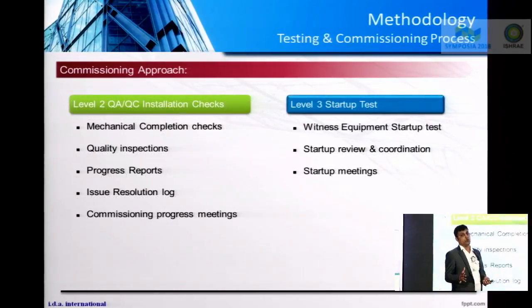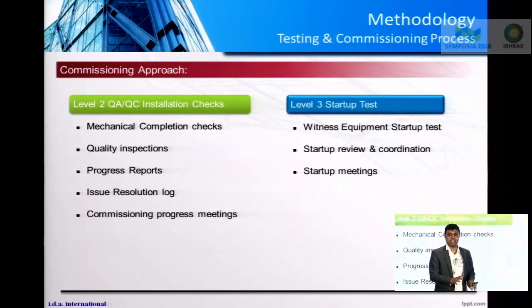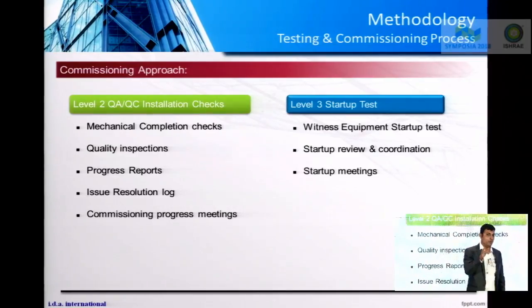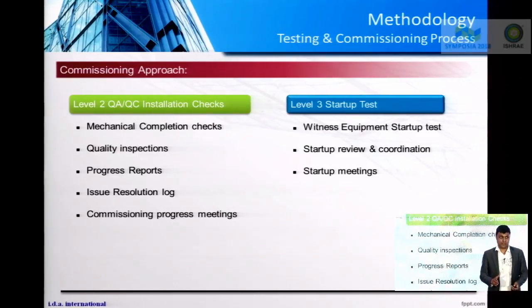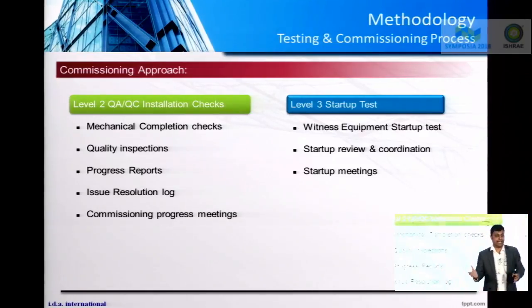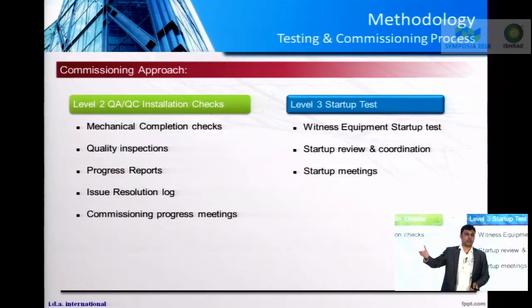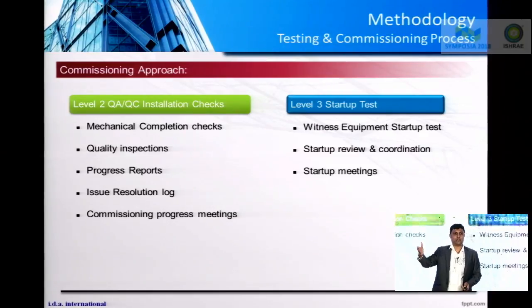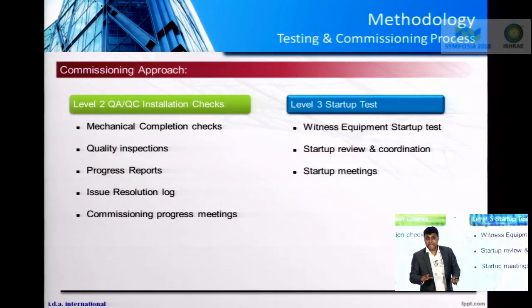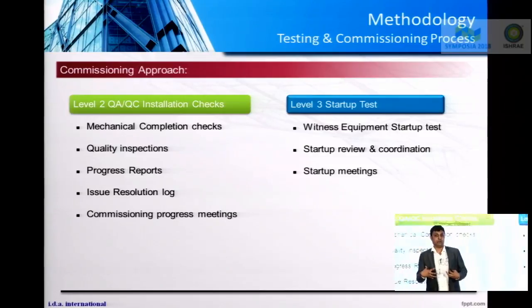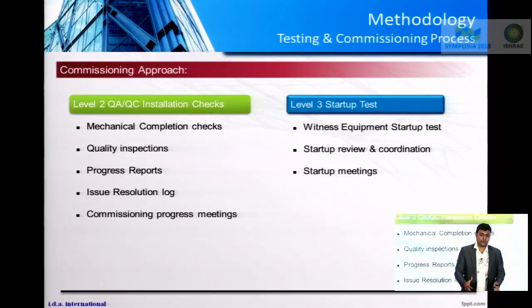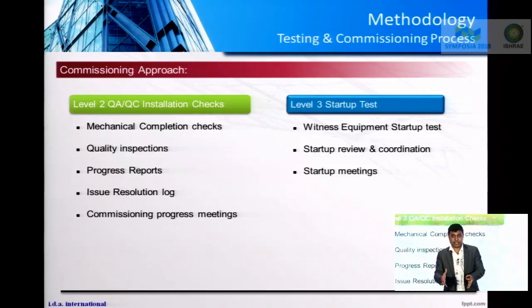Then comes level 2, which is QA/QC, which is quality inspections, quality checks. The moment you jump into the construction stage, you have a lot of equipments which are getting delivered on site. You have a lot of installations which are taking place, like the tray installation, chill water pipes installation. Now, it is the job of the commissioning team to regularly do site visits and ensure the quality is correct.